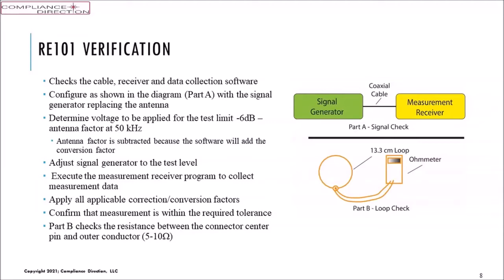That's a pretty wide range here. I usually like to collect this when the antenna comes in and say it's 8 ohms, for instance, and then when it starts deviating from 8, I get concerned that there's something going on inside the loop, where the wiring insulation may become frayed, or we used this loop antenna to do a susceptibility pinpoint and overheated the wiring, insulation meltdown, things like that come into being. So the check is kind of significant, and so is keeping records of what we got. That's why I look at putting a record in the antenna records to say on date X we did the sanity check and it was 8.3 ohms. And then the next time it's done, we record it and say on this date it was checked and it was 8.2 ohms, or whatever. But if we see it going away or becoming more radical, then we need to keep up with that and look at saying there's something going on with the antenna.